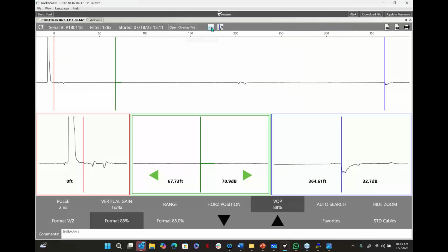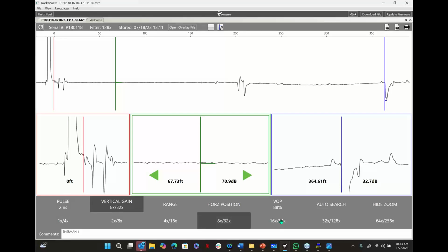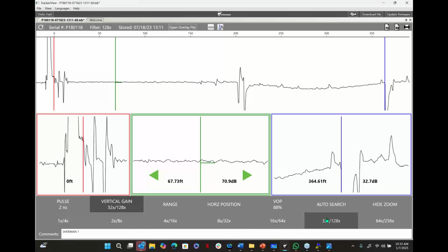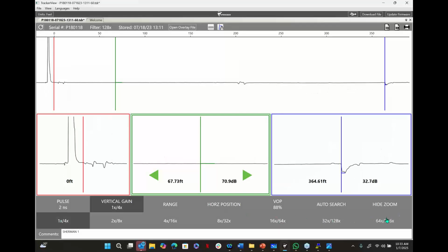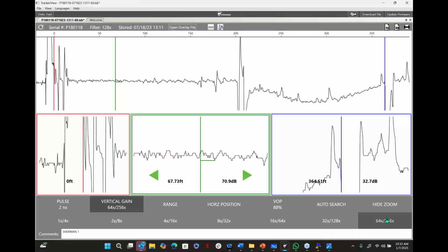Now, I also want to show you, back to my vertical gain question again. Check this out. This was even with my vertical gain all the way down. If I start to gradually increase my vertical gain, you see what I mean, how it can start to make my line look uglier and uglier? Again, this is where it's maybe just right. This is where it's obviously too much.